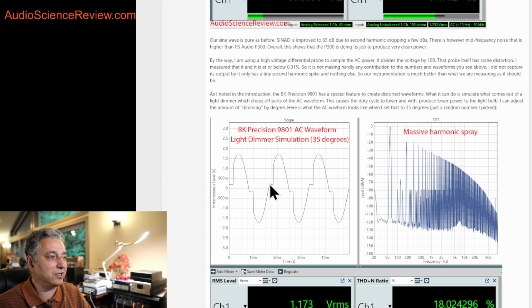You can see it here, and this is programmable in the 9801. I just set it to a random 35 degrees, so 35 out of 360 degrees is set to have no output - that's the flattened section. The waveform is somewhat deformed too, so the emulation isn't perfect. But in this case we want dirty power, and the dirtier the better.